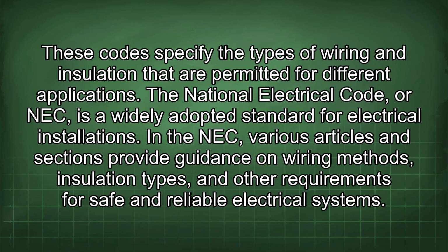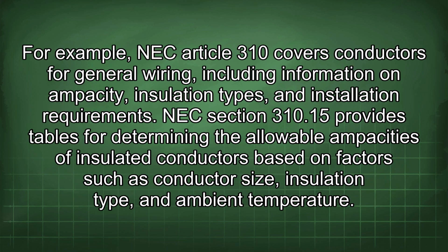The National Electrical Code, or NEC, is a widely adopted standard for electrical installations. In the NEC, various articles and sections provide guidance on wiring methods, insulation types, and other requirements for safe and reliable electrical systems. For example, NEC Article 310 covers conductors for general wiring, including information on ampacity, insulation types, and installation requirements. NEC Section 310.15 provides tables for determining the allowable ampacities of insulated conductors based on factors such as conductor size, insulation type, and ambient temperature.